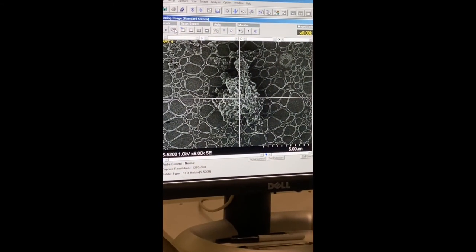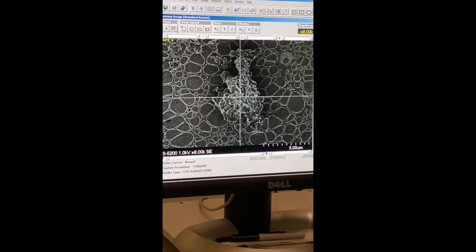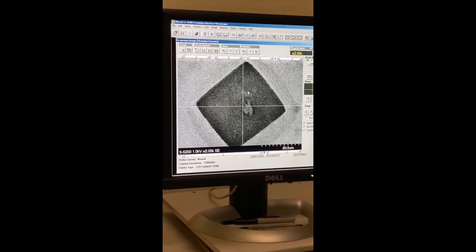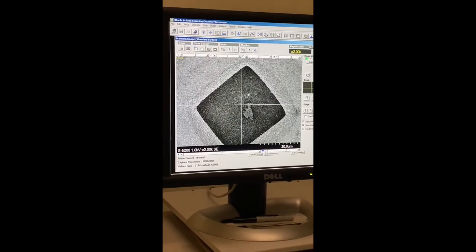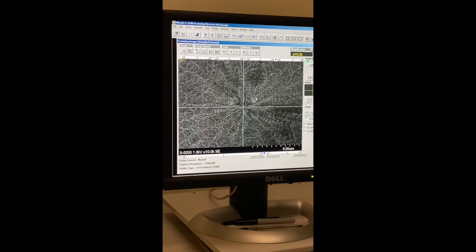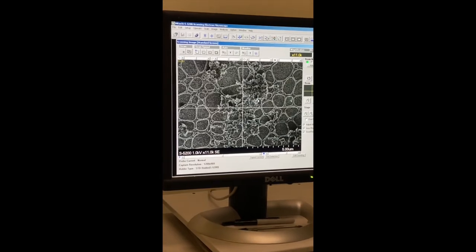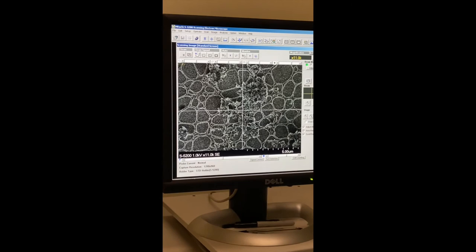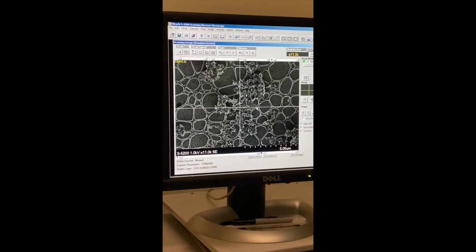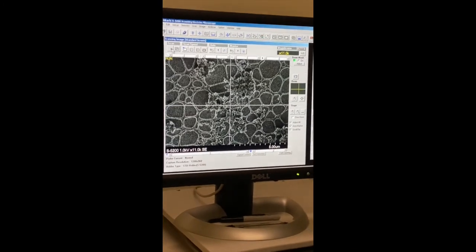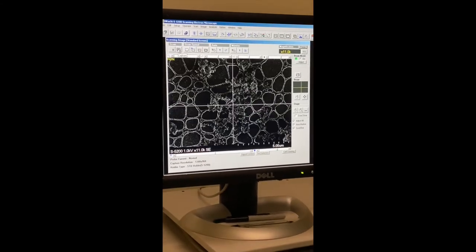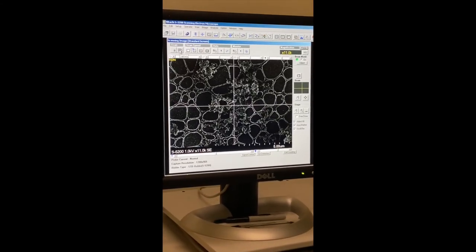However, in non-conducting materials, the electrons are trapped at certain peaks in the material, especially near the top. These electrons will eventually bleed off while you're trying to collect the other scattered electrons and result in a poor image. It can be so bad to the point where a heavily charged sample will actually reflect the electron beam because the incoming negatively charged electrons do not want to touch the negatively ionized surface. And you will get patterns that look like this, that kind of just look like nonsense.